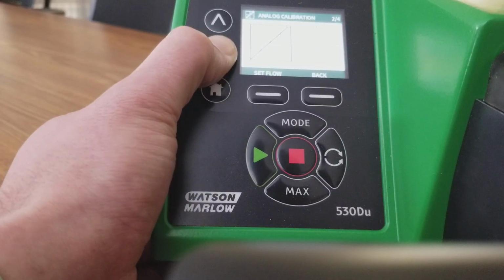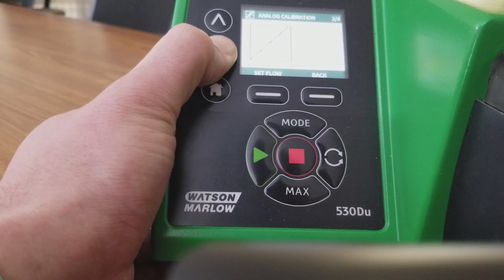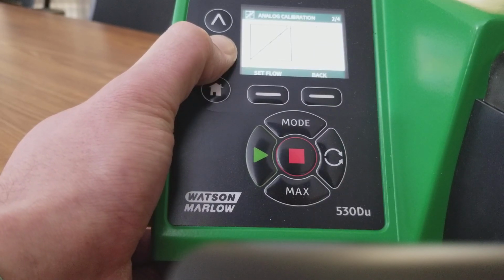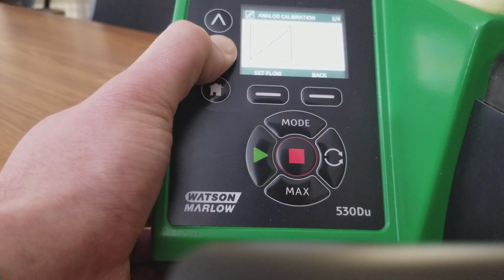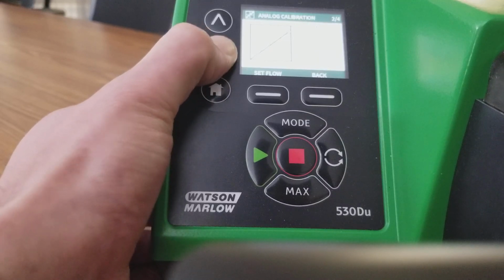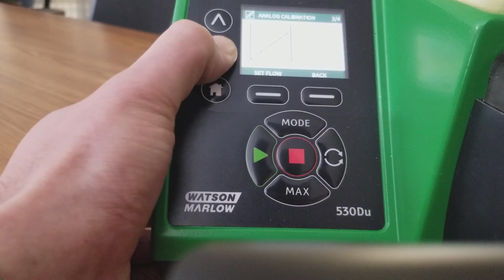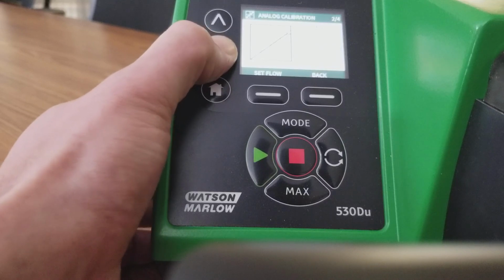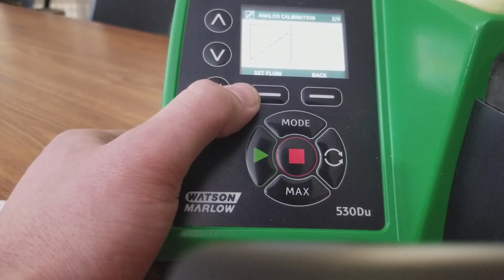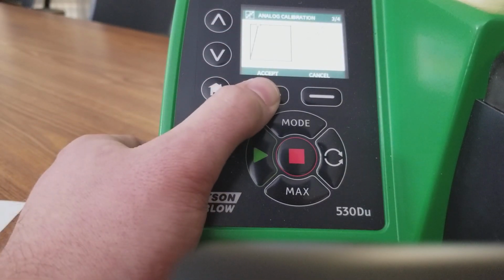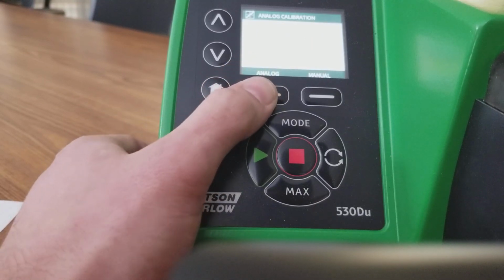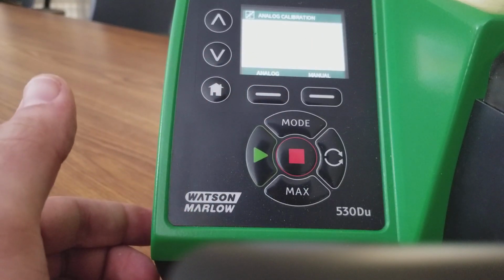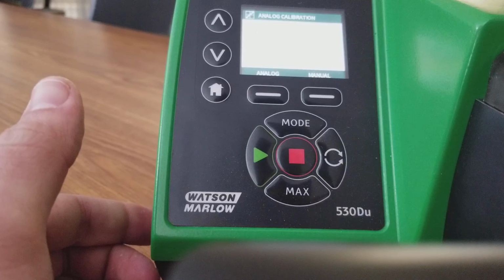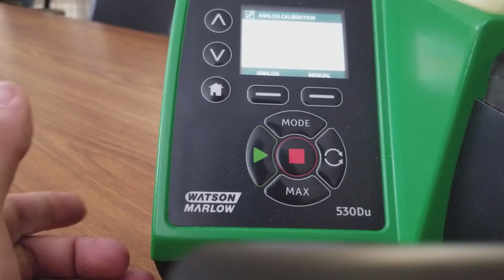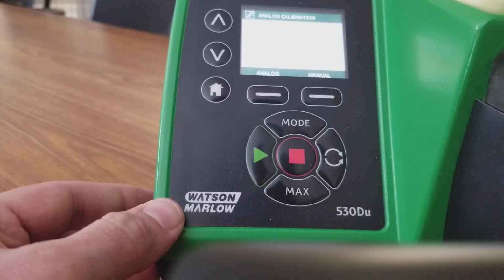So now we could go ahead and put in our 81.45%. Of course, we're going to have to round up because we're only given one decimal place, so we would just put it as 81.5, set flow. Now if we think about it as an analog mode at 20 milliamps, it is a 5 gallon per hour pump. So that way it could be linear with anywhere we were in there.